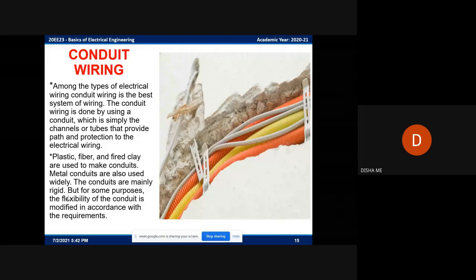Conduit wiring. Among the types of electrical wiring, conduit wiring is the best system of wiring. The conduit wiring is done by using a conduit, which is simply channels or tubes that provide a path and protection to the electrical wiring. Plastic, fiber, and fired clays are used to make conduits. Metal conduits are also used widely. The conduits are mainly rigid, but for some purposes, the flexibility of the conduit is modified in accordance with the requirements.